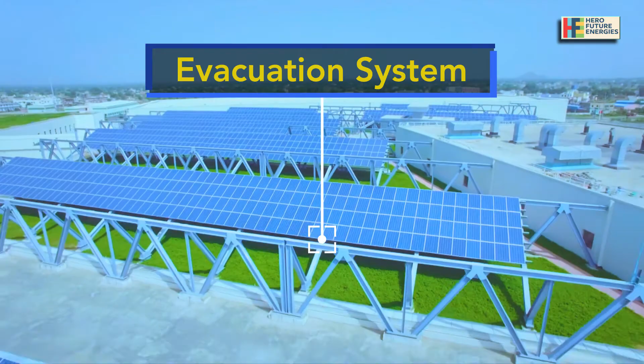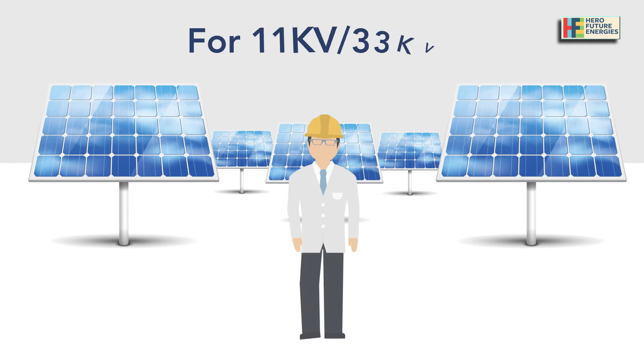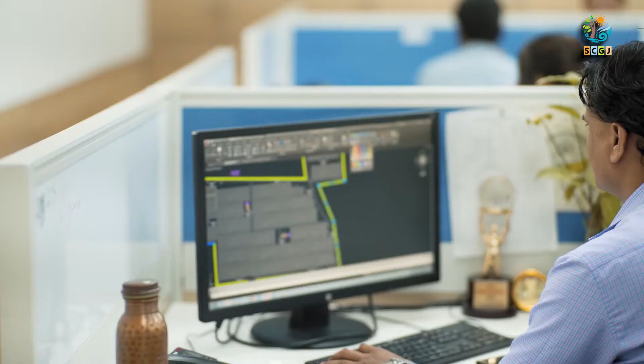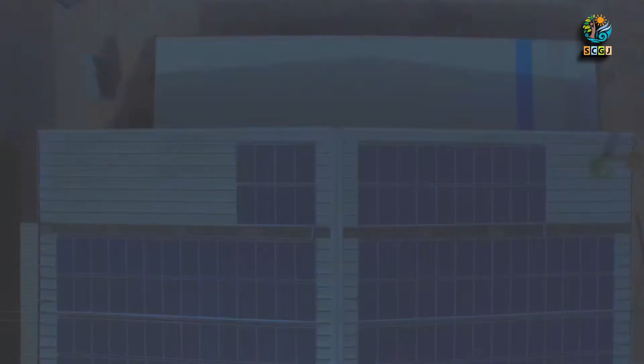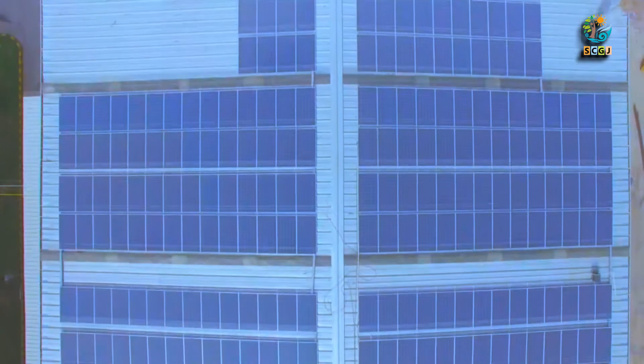During the survey process, identify the evacuation system on site. For example, in case of a 415 volt setup, you do not require any transformer or HT panel. But for 11 kV or 33 kV setups, it is required. Also, design engineers would need information on availability of a spare feeder to integrate it with HT panel and LT panel.